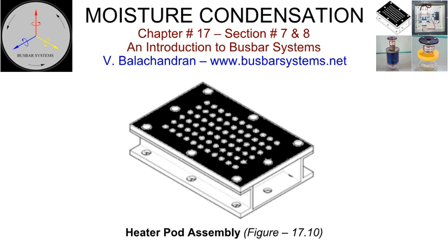The heater shall have a perforated safety cover. It is prudent to specify the maximum temperature rise of the cover. This temperature rise must be tested in a simulated bus duct section. The manufacturer of the heater must also guarantee the total life, in hours, when operating under rated conditions.